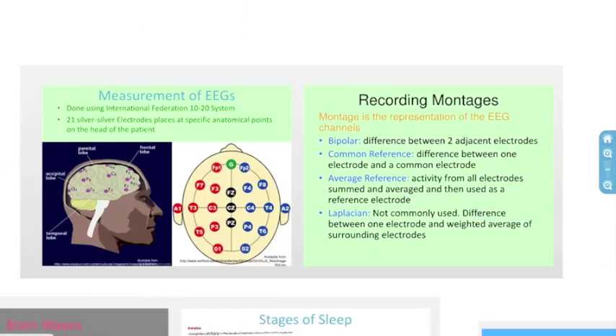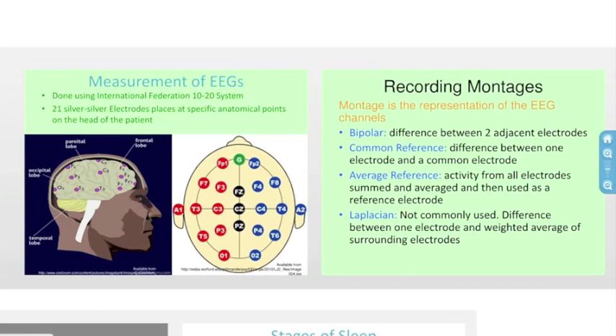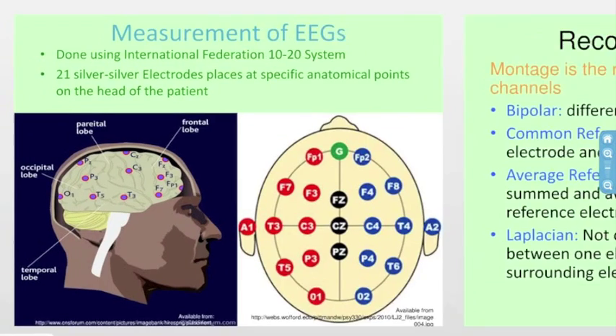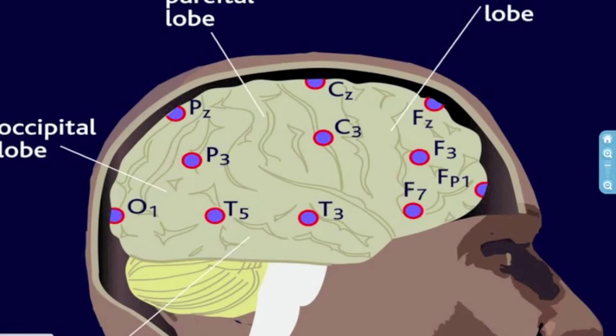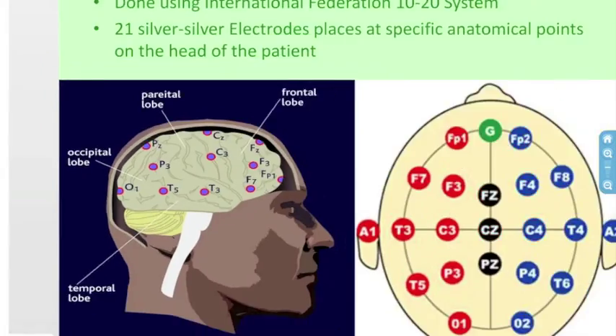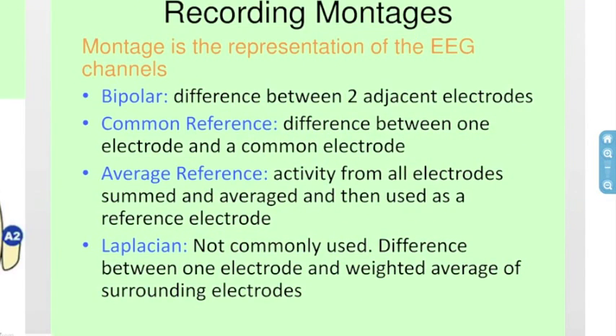EEGs are measured using the International Federation 10-20 system. This involves using 21 silver-silver electrodes placed at specific anatomical points on the head of the patient. A differential signal is amplified and displayed as a channel of EEG activity. This representation of the EEG channels is called a montage. There are four types of montages: bipolar, common reference, average reference, and Laplacian.